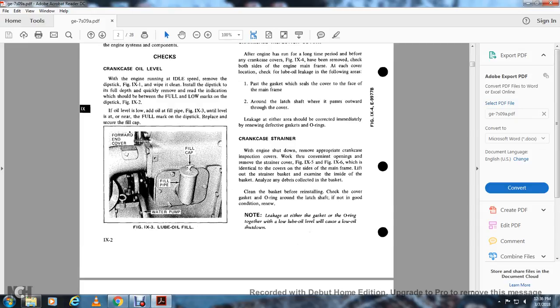For the crankcase strainer, with the engine shut down, remove the appropriate crankcase inspection cover. Work through the convenient opening to remove the strainer cover (figures 9-5 and 9-6). Lift out the strainer basket, examine the inside of the basket, and remove any debris. Clean the basket before reinstalling. Check the cover gasket and O-ring around the latch shaft; if not in good condition, renew. Leakage at either the gasket or O-ring will cause a low lube oil shutdown.